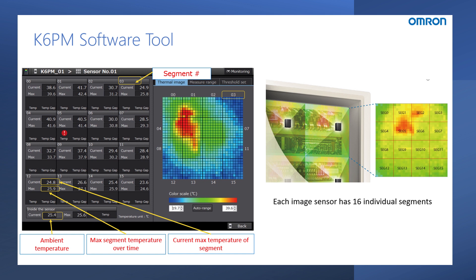You have software to pinpoint and give specific values for each of those 16 component areas. You can use the PC-based software tool to set the limits you want to see within each area, and you can link up to 32 cameras together into the software to cover very large panels or multiple panels, all fed back to the same PC tool. This is quite different from opening a door and using a thermal gun, which only gives you a spot temperature at that moment. This is much more intelligent and user-friendly, and avoids the risk of catastrophic failure from thermal damage within the cabinet.